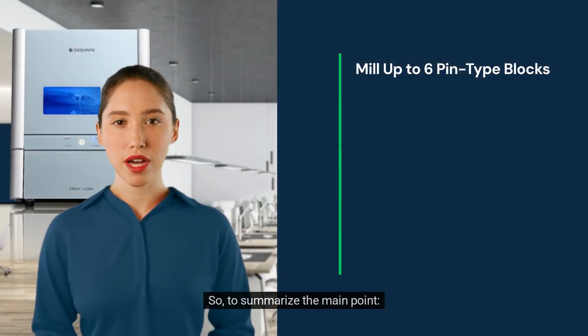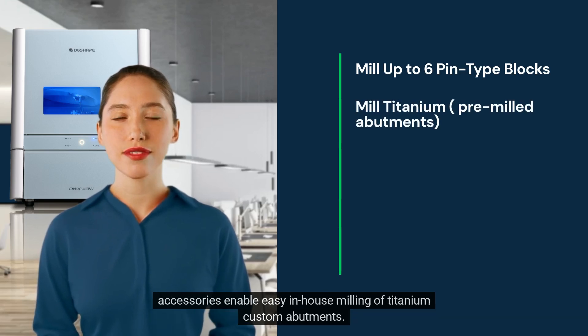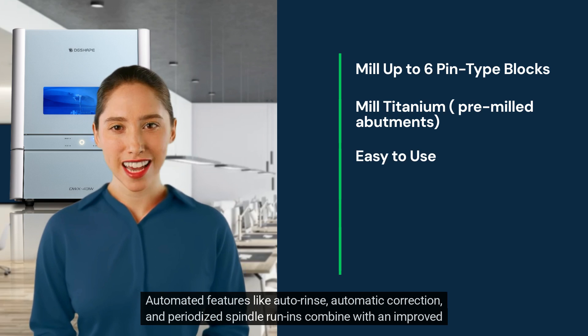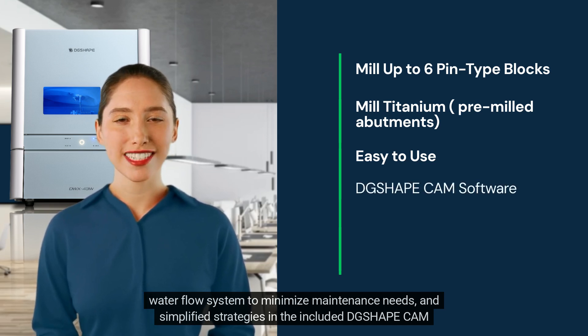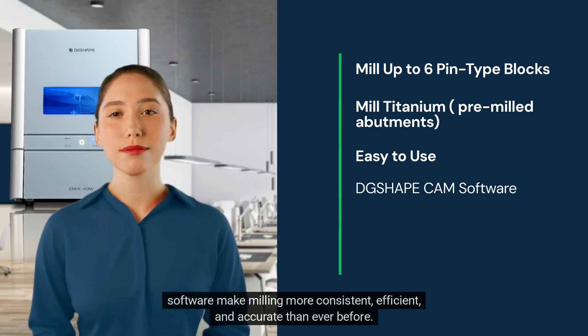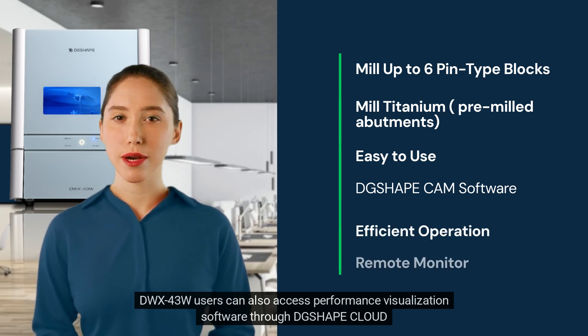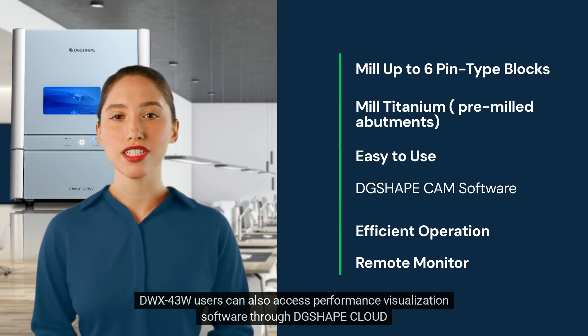To summarize the main points: the multi-pin accessory allows batch milling of up to 6 units of high quality, while additional available accessories enable easy in-house milling of titanium custom abutments. Automated features like auto-rinse, automatic correction, and periodized spindle run-ins combine with an improved water flow system to minimize maintenance needs. Simplified strategies in the included DGSHAPE CAM software make milling more consistent, efficient, and accurate than ever before.